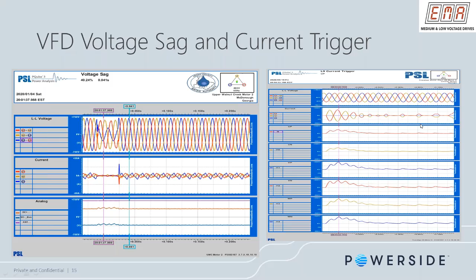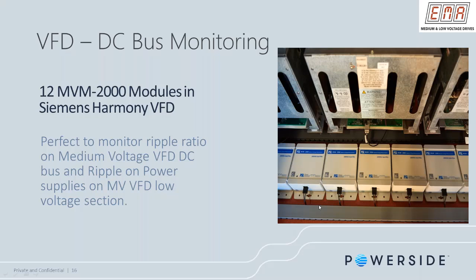This is a picture of a Siemens medium voltage drive. We have 9 power modules, therefore 9 MVM modules that are connected to the power cells, and through the fiber optic are sending data back to the drive scan in the low voltage section of the drive. This actually is a very interesting true story. We had a customer, Henry County in Georgia, where they had a drive that was damaged, and a lot of times customers would ask us to at least analyze the drive and give them a reason why we think the drive failed.